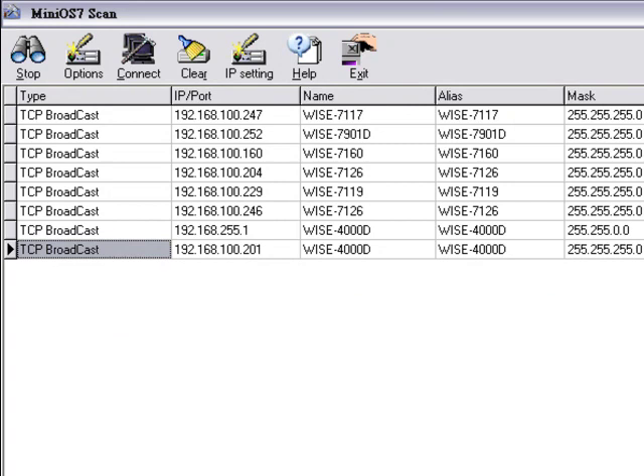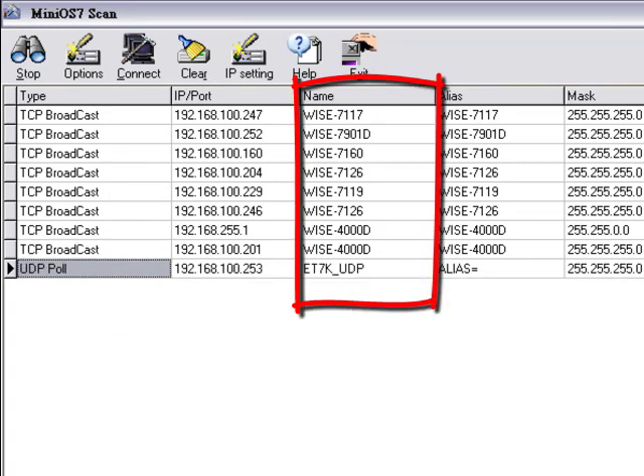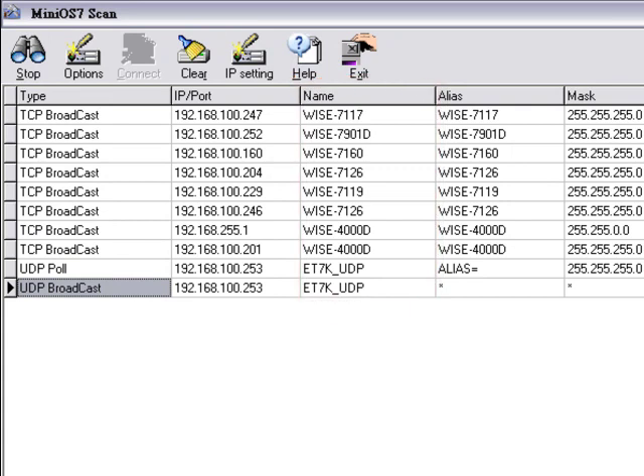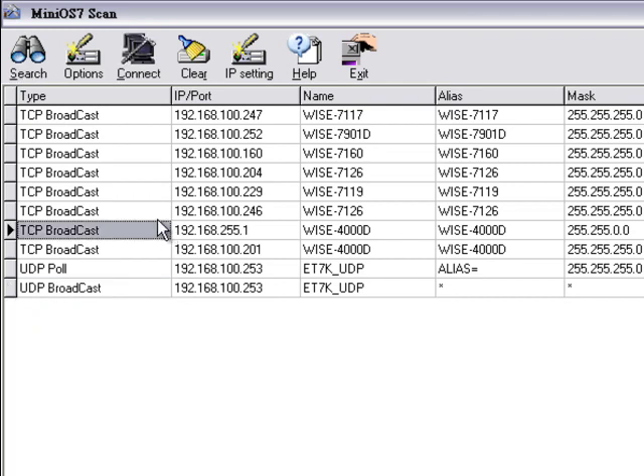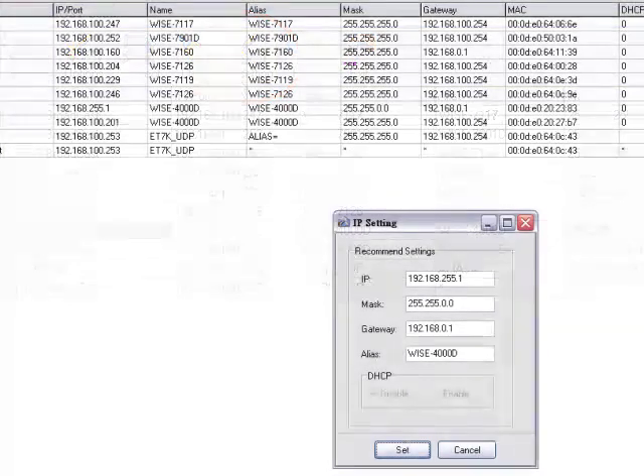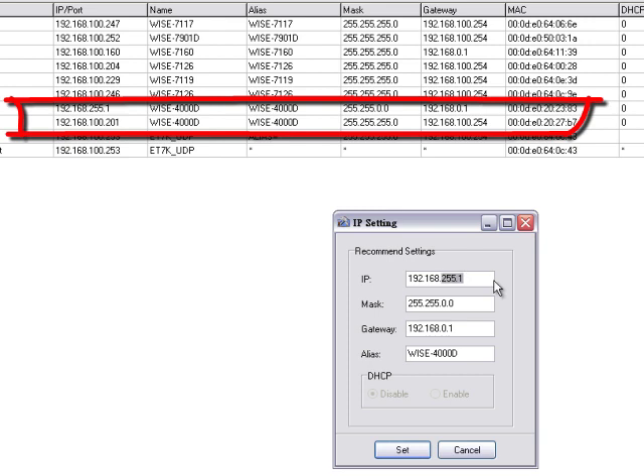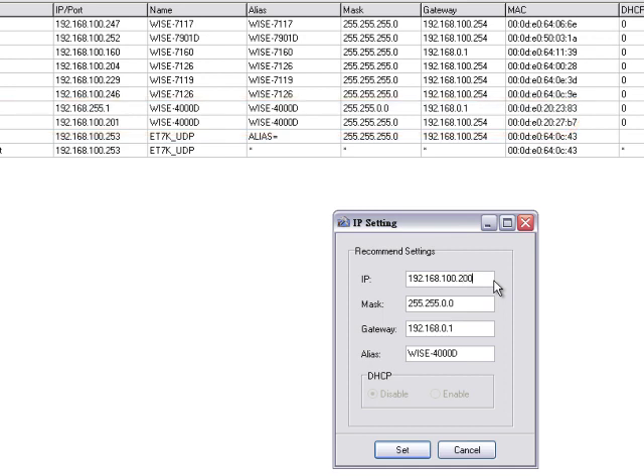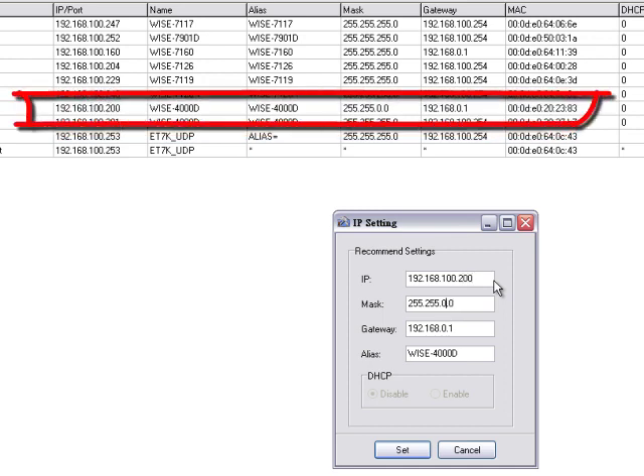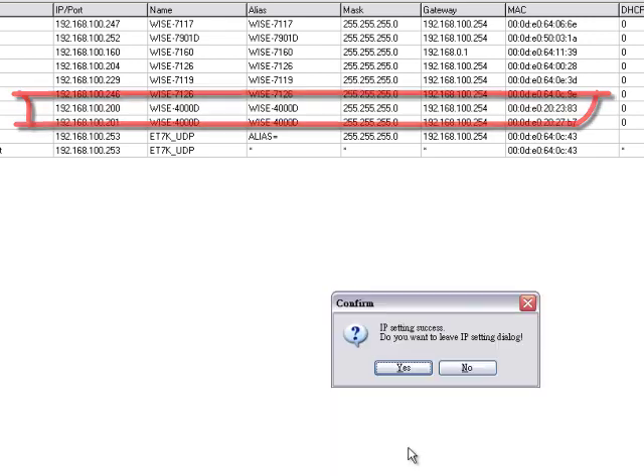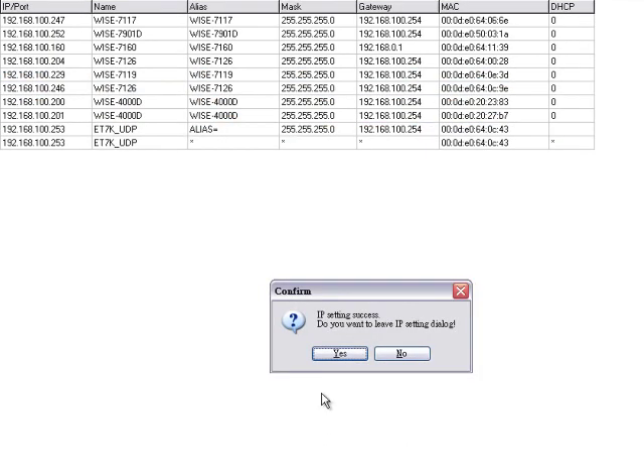With MiniOS7, we can find all WISE controllers that are currently connected to this PC. After searching is finished, all controllers connected will be displayed. Select the target controller and click the IP button. A window will appear for you to assign the IP to the controller. Each controller is given a default IP address, which may not be consistent with your network. It is recommended that you set up your PC IP in the same network region as your WISE controller, so your PC can find the WISE controller and you can configure related logic control operations via the internet.